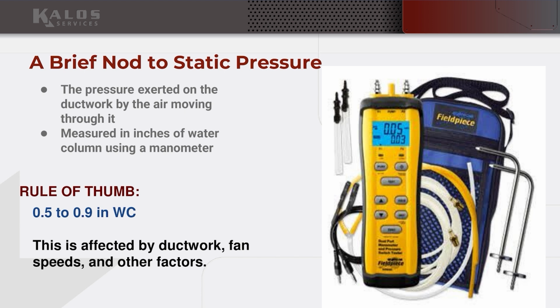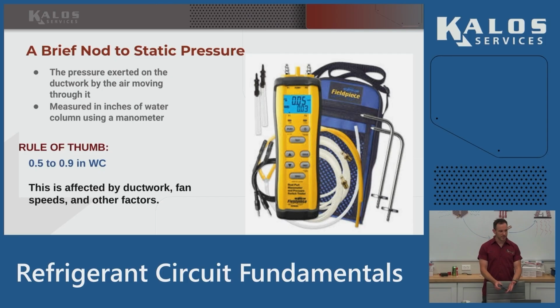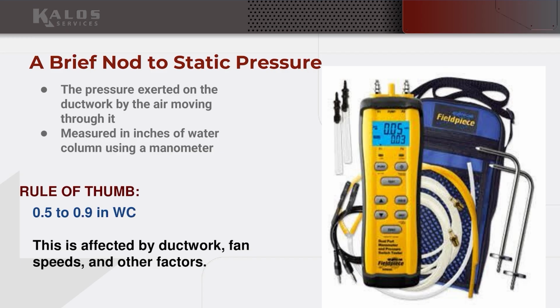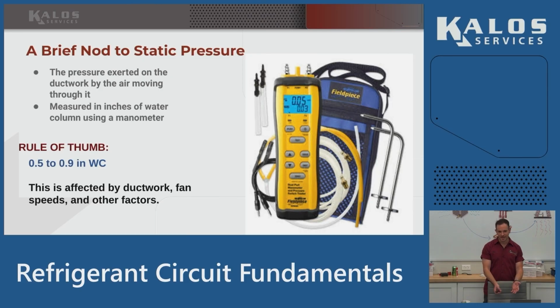We'll briefly talk about static pressure. This isn't something that we normally measure. It's not one of my 5 pillars, but it is something to know. The ductwork does play a factor. One of the other problems you can have with airflow restrictions isn't just the filter or the coil. You can have issues with your ductwork causing poor airflow, like restrictions from a crushed duct or a crushed return. It's not letting the system breathe. You might not be able to see that visually, but you could if you used your manometer. You would see a high static pressure. Static pressure is basically the same way we measure refrigerant pressure in the pipes. We're measuring the pressure of the air in the ductwork itself. That's what our manometer is telling us. We won't get into how to measure it, but it is a thing. Just be aware it exists.